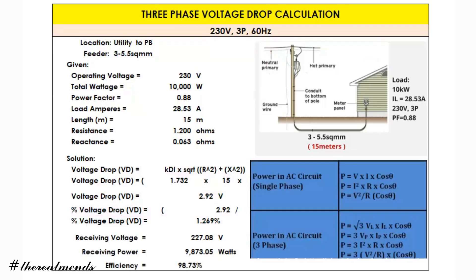If you want to get the receiving voltage at the end — at the meter panel — just subtract 230 volts by 2.92, giving us 227.08 volts. To get the receiving power, we use the power formula. In AC circuits for single phase, power equals voltage times current times cosine theta.